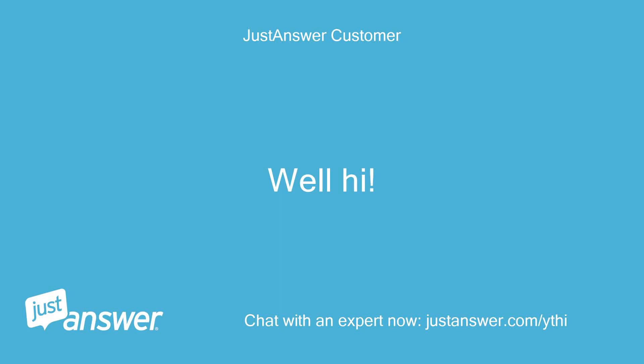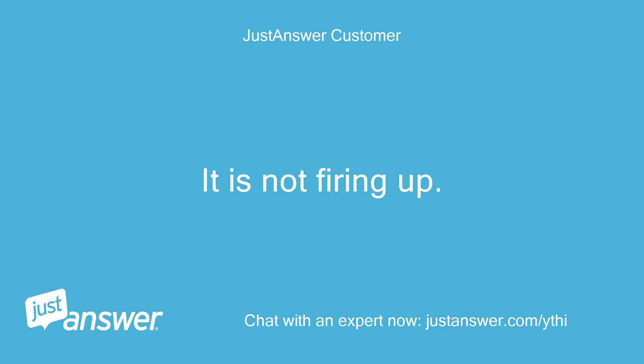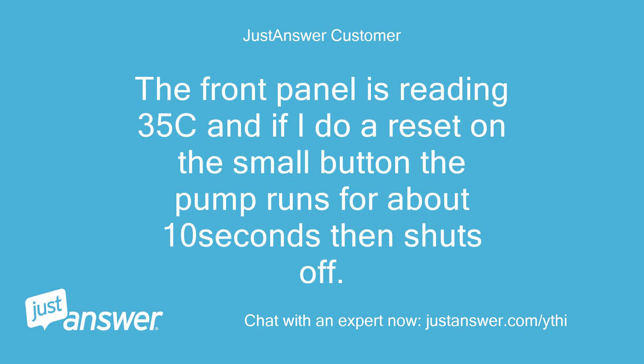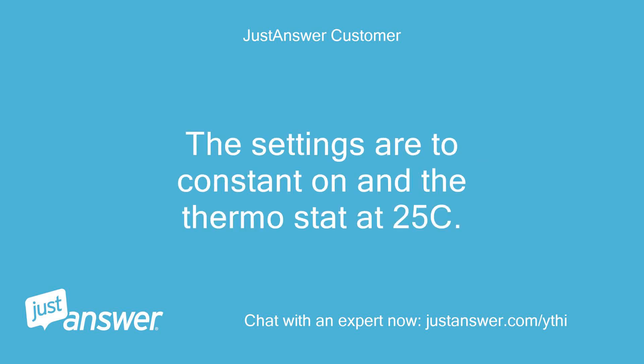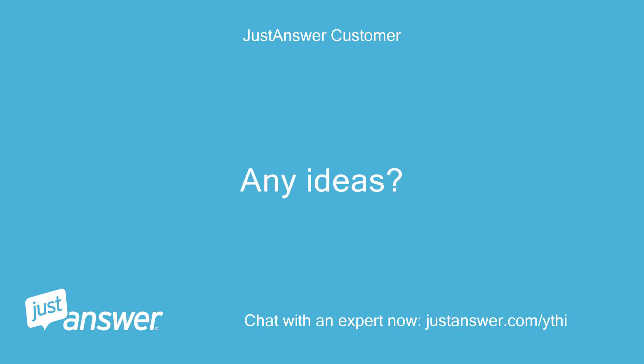I am troubleshooting our British Gas 330 Plus boiler. It is not firing up. I have made all the usual checks and there are no fault codes showing. The front panel is reading 35°C and if I do a reset on the small button, the pump runs for about 10 seconds then shuts off. The boiler doesn't fire up at all. The settings are set to constant on and the thermostat at 25°C. I have checked the pump upstairs and no air comes out, only water. Any ideas?